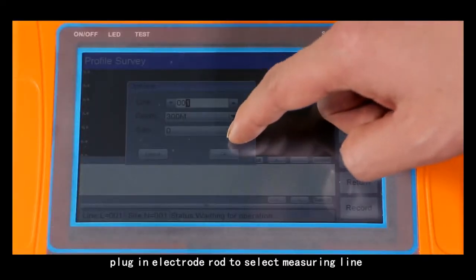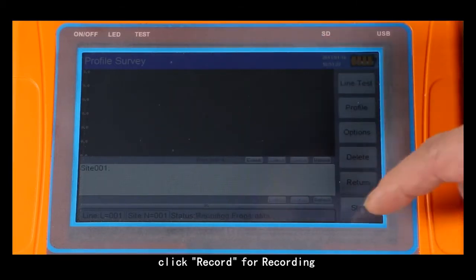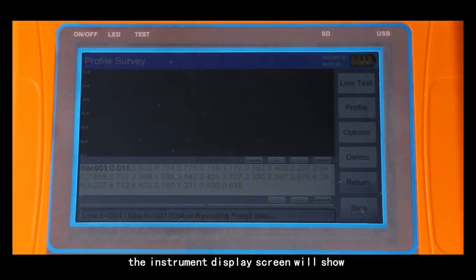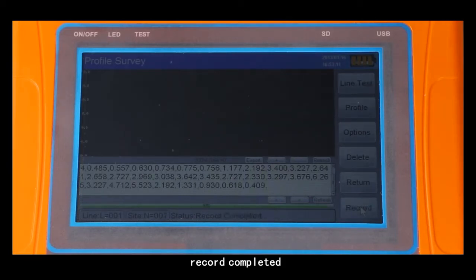Plug an electrode rod to select a measuring line. Click record for recording. After data collection, the instrument display screen will show record completed with a reminder sound.